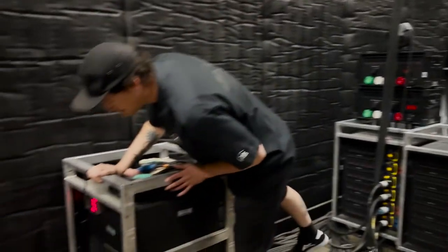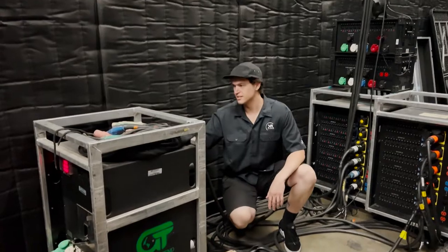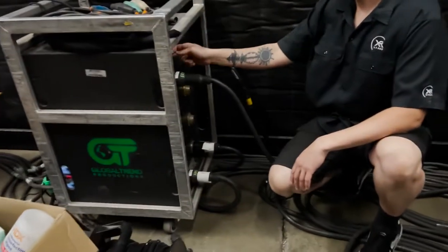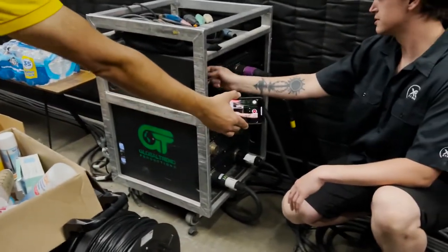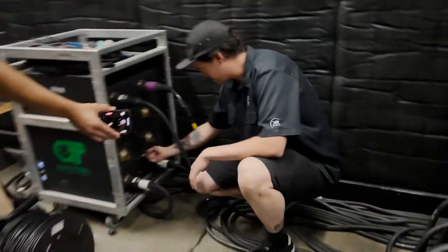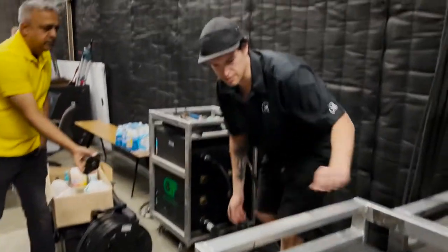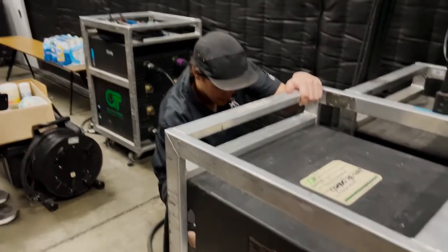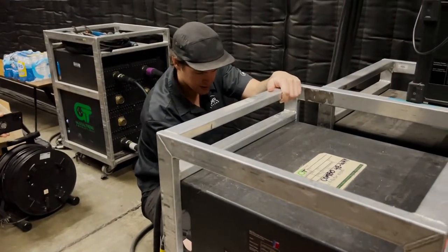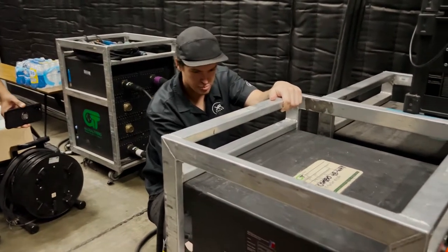So we don't fry the LED with having too much current at once. We come here and we turn on each 20-amp breaker one at a time. We have all of these Socapex cables, and each Socapex cable has six circuits. So we turn on each circuit one at a time or three at a time. We just don't want all 2,500 amps to go from zero to full power — you can pop a breaker.